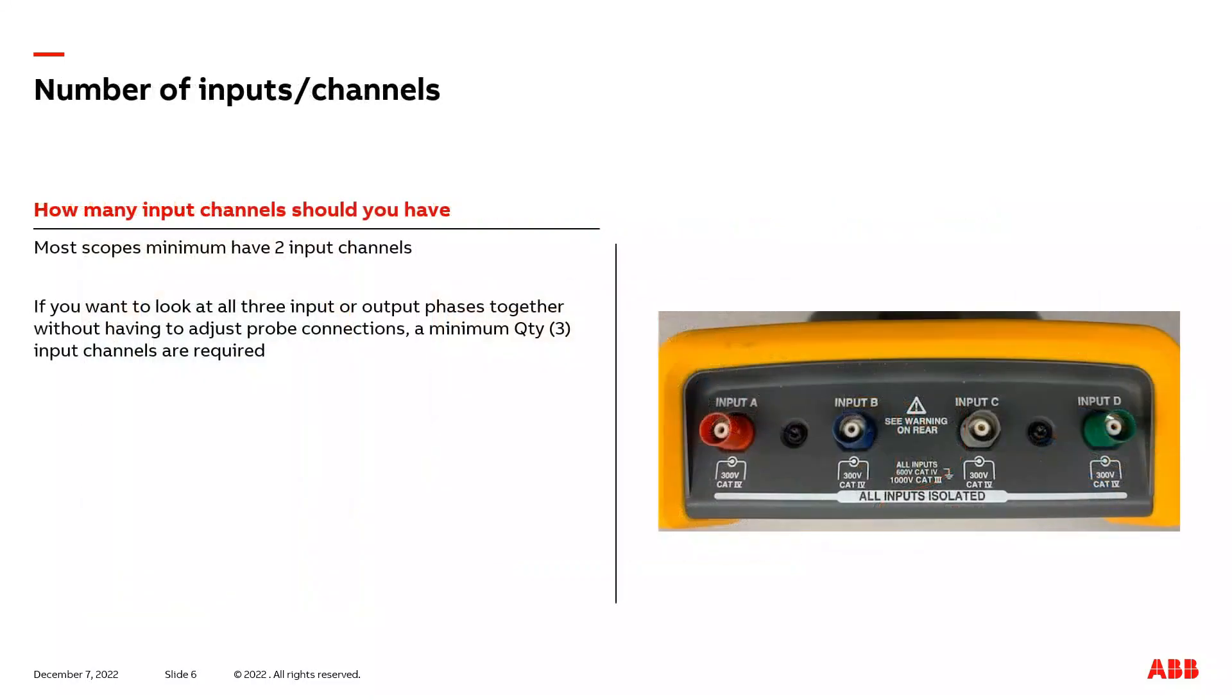So how many input channels should your scope have? I recommend your scope have a minimum of quantity three input channels. The reason I say quantity three is because VFDs on the input side and output side are three phase devices. And we also have to think about lockout tagout safety procedures and time spent on the job. If I lockout and tagout the drive once, make all my connections either voltage probes or current probes to the drive and then to the scope, I then can turn the VFD back on and individually look at all the individual phases at once. Or I could look at all the phases at one time on the scope. But I'm not having to re-lockout tagout the VFD to move a voltage or current probe every time I want to look at a different channel. So that's why quantity three input channels is a benefit on your scope.